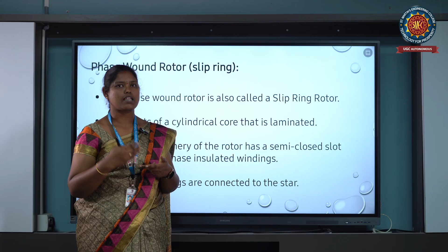Okay, so external resistance can be added through the slip ring, which is a disadvantage in the case of the squirrel cage type. So slip ring type will give us control of the speed of the rotor, and second, starting torque will be increased, which is also a disadvantage that we have seen in the squirrel cage type. So what are the things that we have in this? First one is the slip ring, which is present in the machine, and second is brushes.